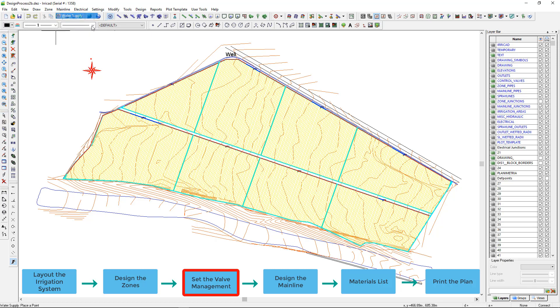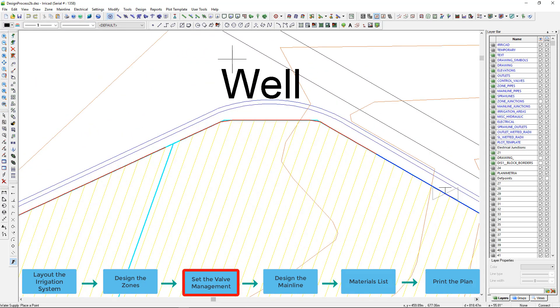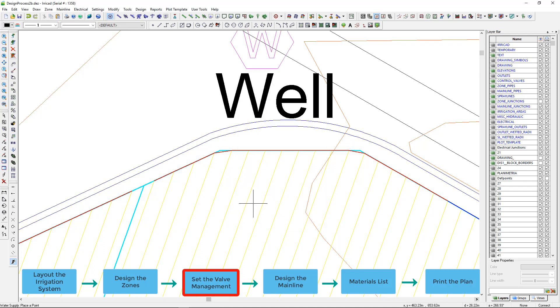Firstly, we should place a water supply. A water supply is placed to specify where water from a well, dam, river outtake, or water at the farm gate is available. When specifying a water supply, you can either set the pressure to a known head or ask Irricad to calculate the required pressures. In this case, I will ask Irricad to calculate the pressure for me.